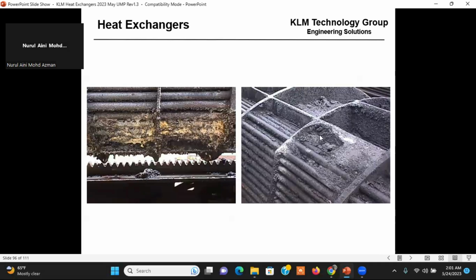So anyway, what I need to do is put little notches right here so that this will flow through. That baffle doesn't need to come all the way to the ground. I just need to put little notches. All that trash will move. All right. The reason the vendors don't put the notches is the notches make it a little less efficient. But after you've lost 20% of the efficiency, it's way less efficient. So it's slightly less efficient with the notches when you first start it up, but you retain your efficiency over the life of the heat exchanger. All right, so if I'm going to design for fouling, I'm going to put small notches right here to have this flow so I don't fill it up with trash.